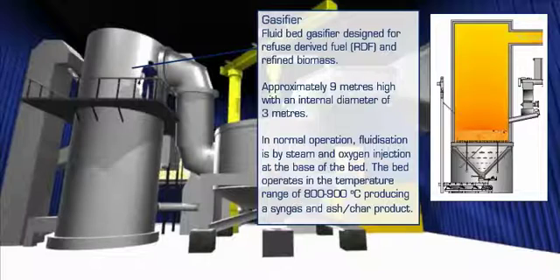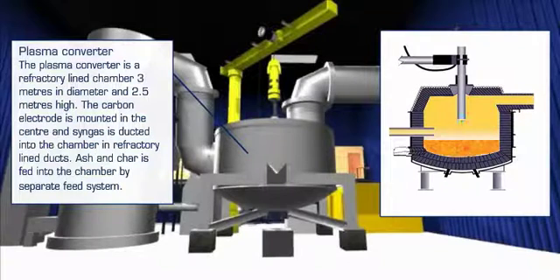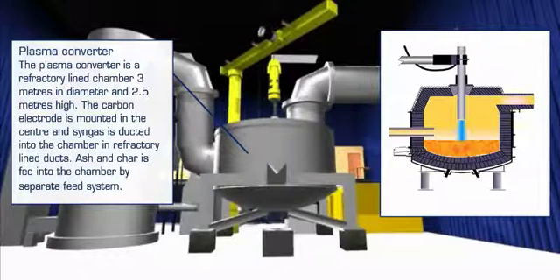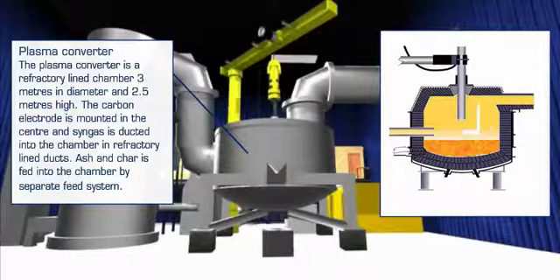A small percentage of the input material — a mixture of ash and char — is removed from the base of the bed and transferred to the plasma converter. The plasma converter is a refractory lined chamber with a carbon electrode and electrode control equipment mounted at the centre of the chamber roof. On entry into the plasma converter, the syngas is forced to swirl around the chamber, allowing maximum time for the gas to be exposed to the high temperatures and intense ultraviolet light of the electrode arc before exiting through a refractory lined duct for further processing. The ash and chars are also treated in the plasma converter, becoming a molten product which is continually removed, cooled and processed into a recyclable aggregate.